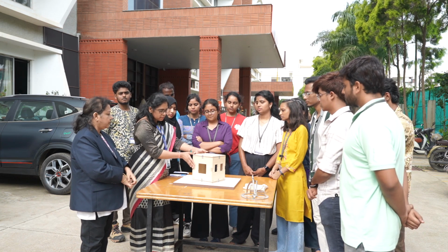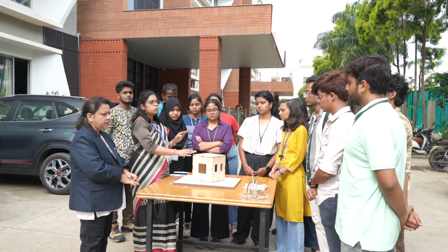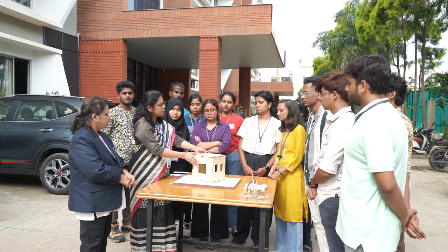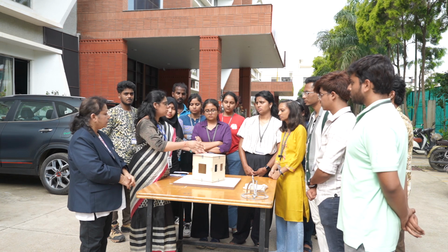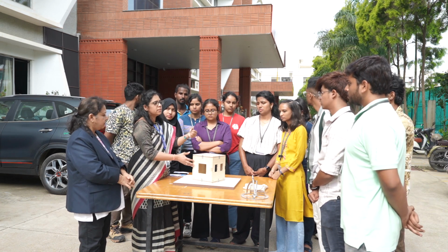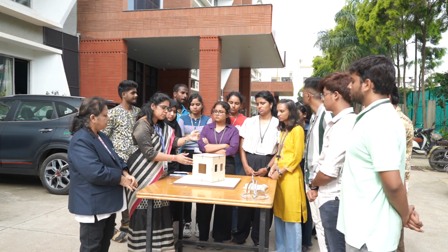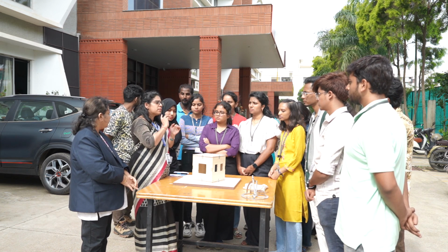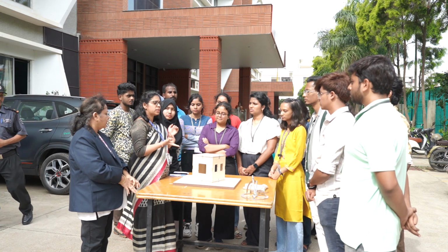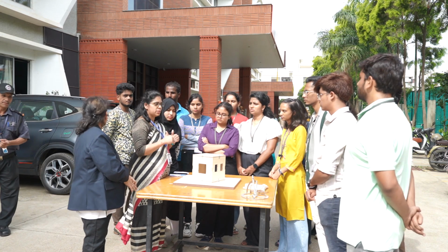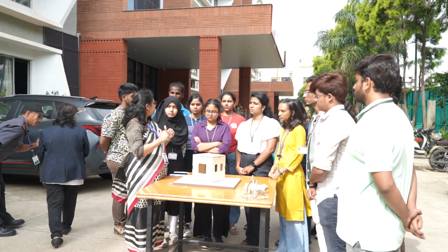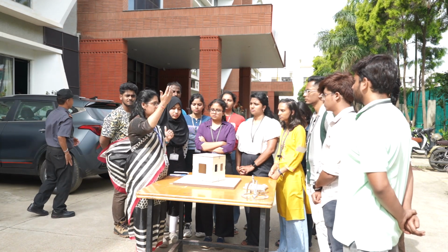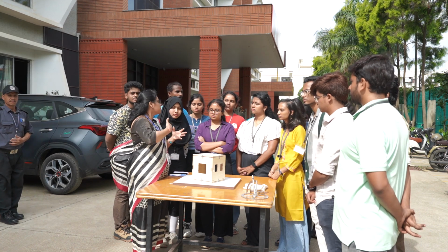The first thing starts with the orientation of the building, because the sun is very harsh when it is in the direction of east and west. So you align the building in such a way that your longer axis is aligned towards north-south, so that less heat energy is transferred inside the building. Once you reduce the heat energy transferred inside, automatically the energy usage of the mechanical equipment I use to make my space comfortable gets reduced. Indirectly it helps in reducing the carbon emission into the atmosphere, the carbon emitted in production of that energy.